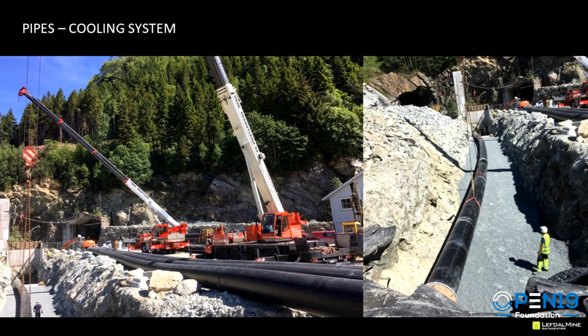So we have a 500 meter deep fjord, so we go down 50 meters and pick up 8-degree water, 24/7, 365. One modus of operandi. No hot days, no polluted air. There is cold seawater, 8 degrees. We take it through 900 millimeter PE pipes just above surface and down to level 3 in the mine.